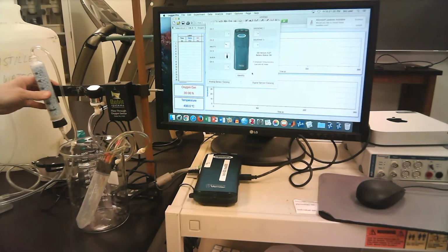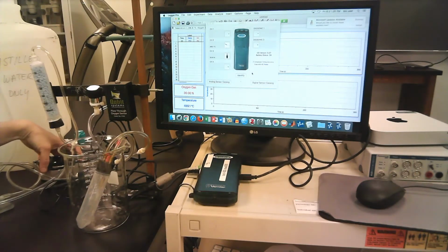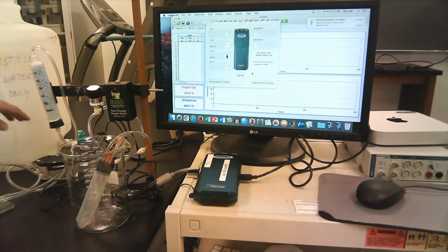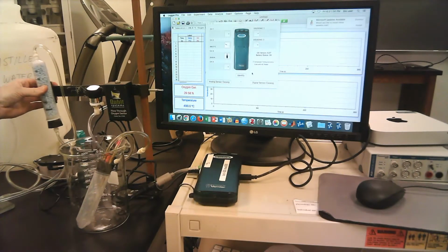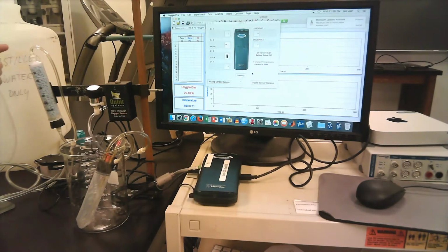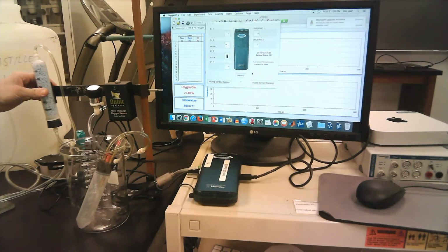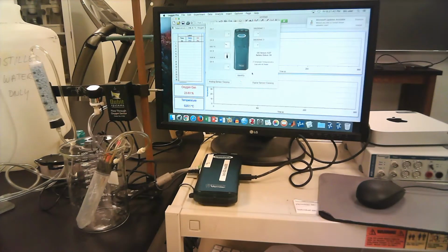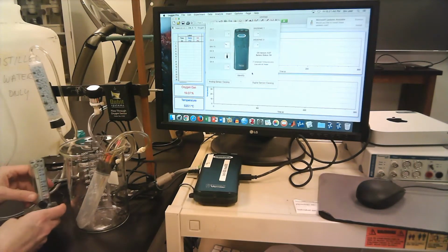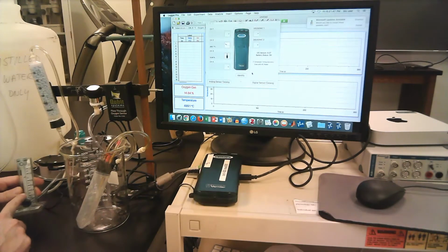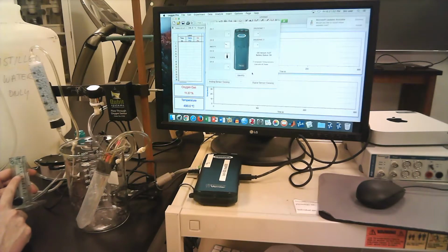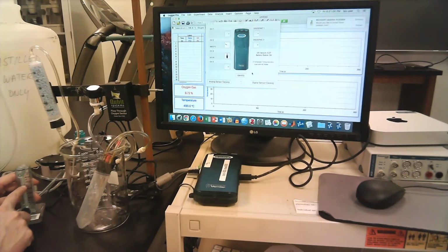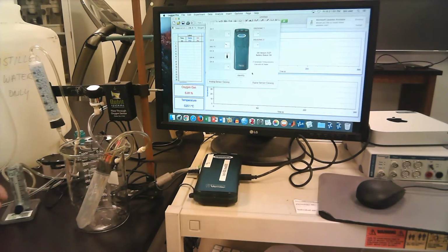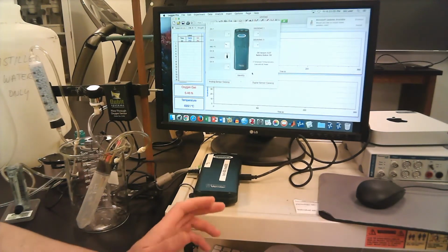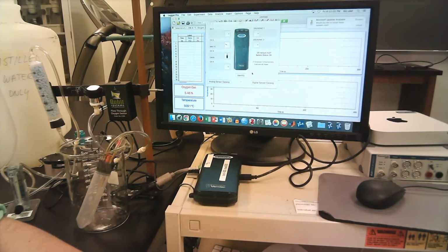Just as a general note, try to avoid running the pump if you're not actually measuring something, because if you continually run it, you'll just wind up burning all the way through your scrubber, and then you won't be able to scrub out water any longer. So now I've got gas flowing from this. The other thing that I can see at this point is in my flow meter. I can actually see the flow moving. And this is moving at a rate of close to between 0.9 and 1 liters per minute at the moment. The flow rate's not too important at this point in time. We can just let it flow with what it's got.